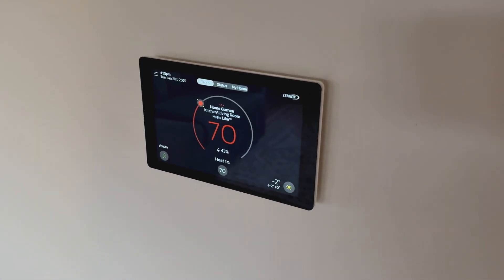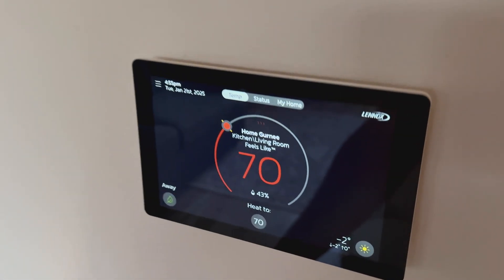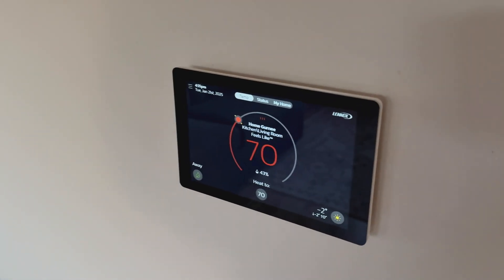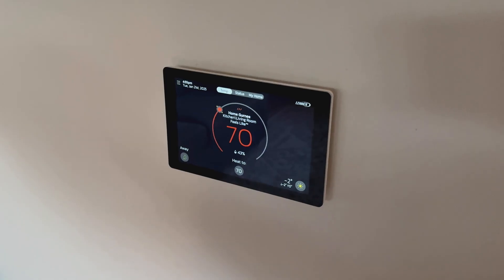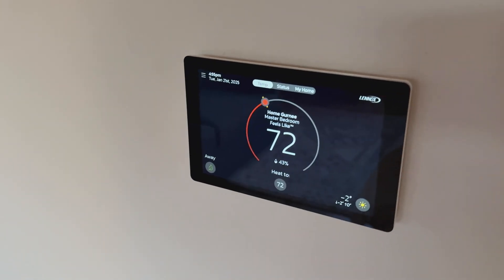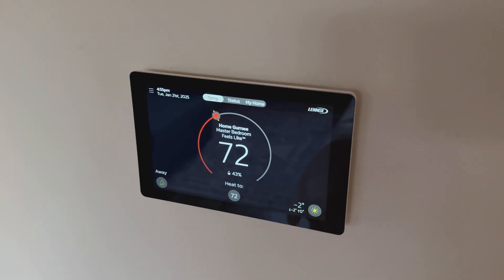Here is the main thermostat that controls the system. It's the Lennox S40 smart thermostat, which is what is called a communicating thermostat — that's what makes the system really smart. This thermostat can communicate several parameters of operation with the rest of the equipment: the outdoor unit, the gas furnace, and the thermostat itself. It's constantly monitoring outdoor temperature, indoor temperature, and humidity levels, making very precise adjustments to the equipment operation for comfort and efficiency.